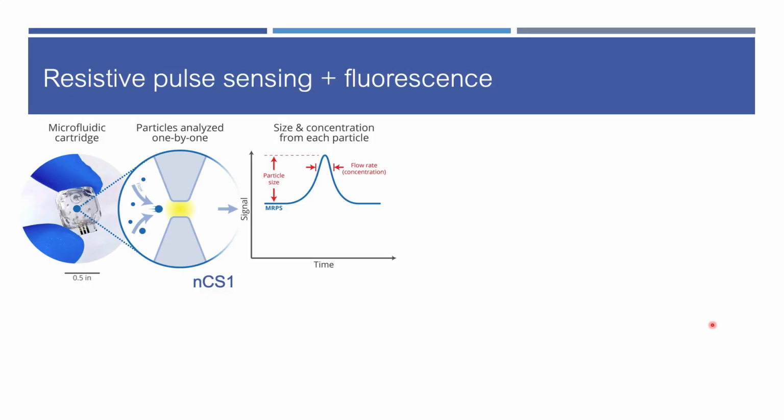You've heard a little bit about resistive pulse sensing, which is a technique where you have a nanoconstriction. Particles move through that and affect the electrical properties of that constriction. If you can measure the magnitude of the signal change during a particle translocation across this channel and the time it takes to pass, you can actually extract a particle concentration and size pretty accurately from solution.